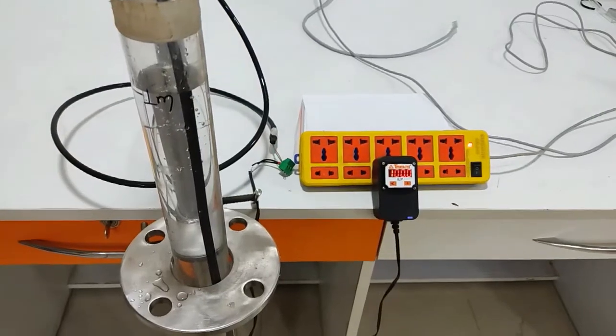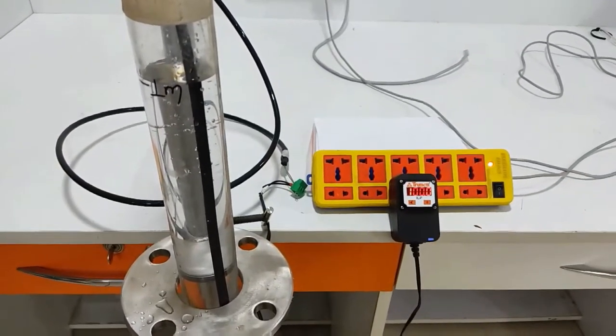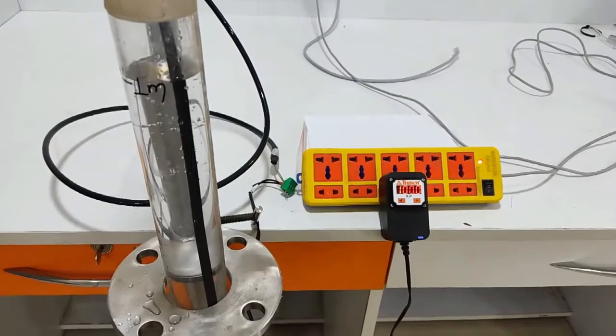As you see, when the water reaches the 1 meter mark, our display is showing 100% for 20 mA.